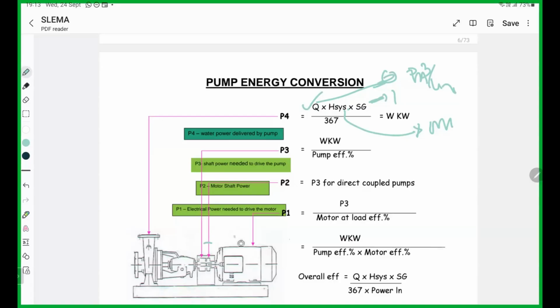Then P1, that motor efficiency, if you divide P3 by the motor efficiency, then you can get this input power. Then finally we can calculate the overall efficiency: flow rate into head into specific gravity divided by 367, divided by power in. This is the system overall efficiency, right? It is important to calculate this before you start your work. You have to know what the efficiency is. This sort of thing is a very easy calculation, right?